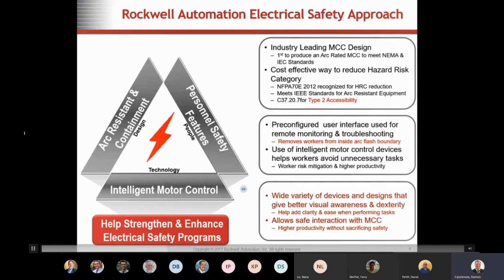Now today, what we're going to talk about is the bottom one, and that's going to be the SecureConnect. So what this is doing is allowing safe interaction with the MCC by removing the line side power of the fuse disconnect and or the circuit breaker. We talked about that. Just because you have the handle off, that does not mean that the top of the circuit breaker or the fusible disconnect is cold. It still has hot wires being fed from the stabs that are plugged into the vertical bus.